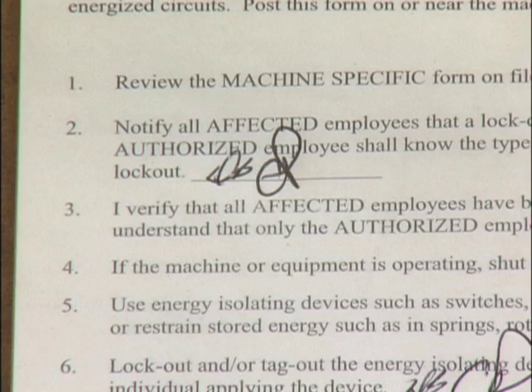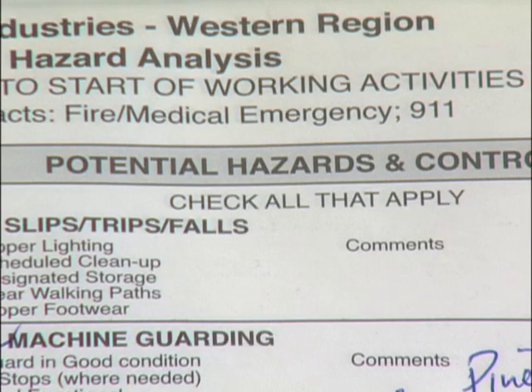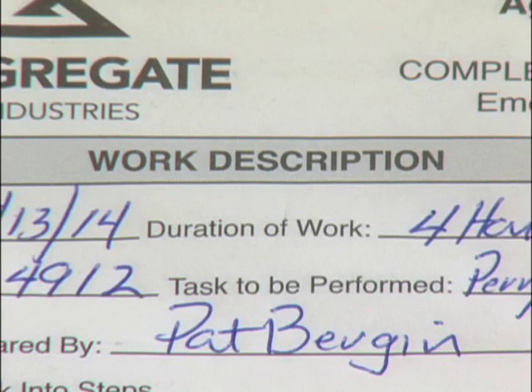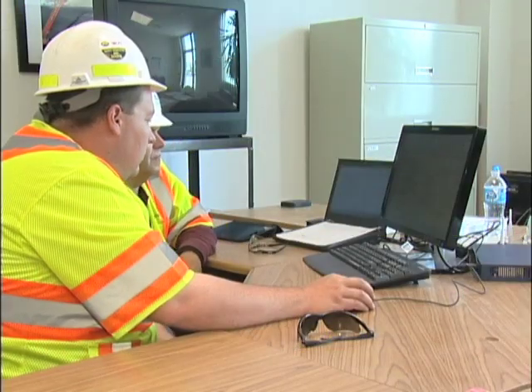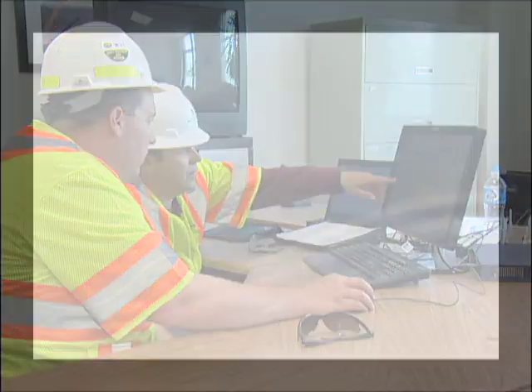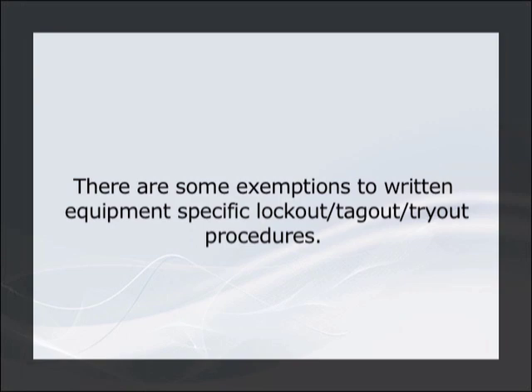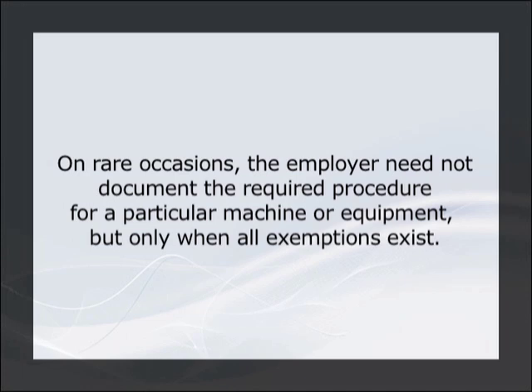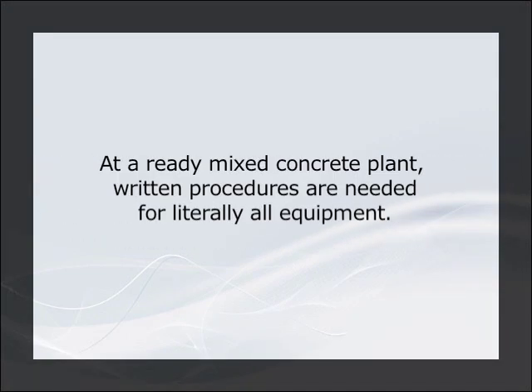The logbook identifies the machine procedure number, employee or employees, and/or outside contractors, action to be completed and why, date and time of the lockout, tagout, tryout, and date and time that the machine or equipment is returned to service. There are some exemptions to written equipment-specific lockout, tagout, and tryout procedures, and on rare occasions, the employer need not document the required procedure for a particular machine or equipment, but only when all of these exemptions exist. At a ready-mix concrete plant, written procedures are needed for literally all equipment.